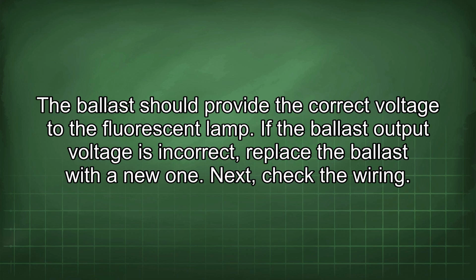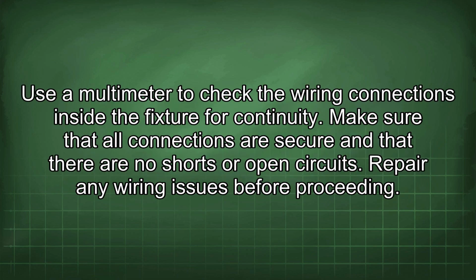Next, check the wiring. Use a multimeter to check the wiring connections inside the fixture for continuity. Make sure that all connections are secure and that there are no shorts or open circuits. Repair any wiring issues before proceeding.